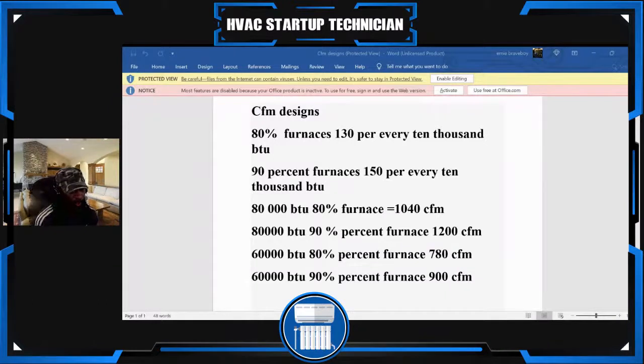We're going to go a little deeper, and if you look at the slide I have up there, I did different numbers. I said if I had an 80,000 BTU 80% furnace, I was getting 1040. But what if we were doing a 60,000 BTU furnace? How would you work out how much CFM you need? You take that same 130. We're sticking with 80%, not going to 90%. I will touch on 90% in a little bit. We take that 130 times 6. You see how easy it is to work out? If you do 130 times 6, that gives you 780 CFM.